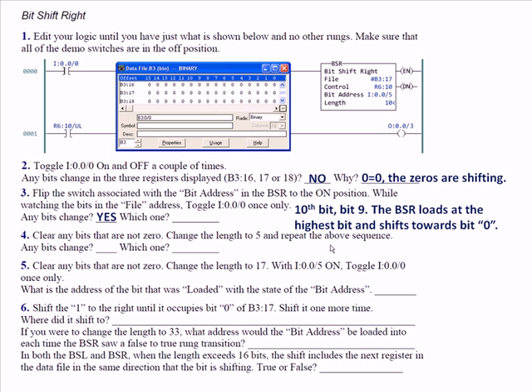Clear any bits that are not 0 in B3:16, 17, and 18. Change the length to 5 and repeat. The fifth bit of a length of 5 is bit 4, so bit 4 changes. Then clear again, change the length to 17, turn Input 5 on, and toggle Input 0 once only. The bit loaded with the state of the bit address is B3:18 bit 0. So with a length of 17, whether using BSL or BSR, you're working on the same group of 17 bits — the only difference is you load at the highest bit instead of the lowest and shift in the opposite direction.